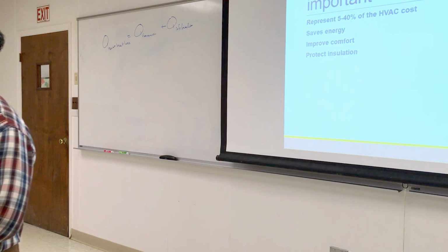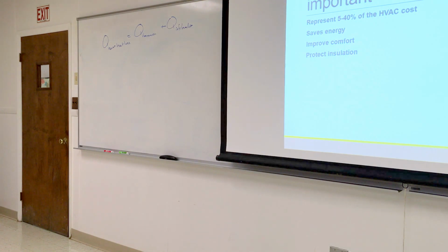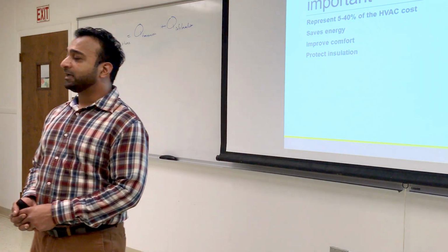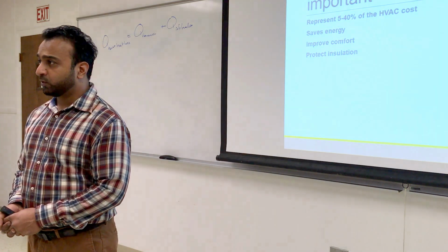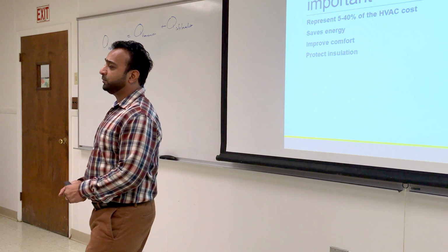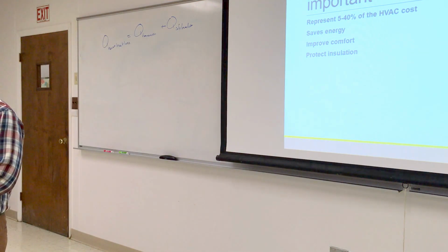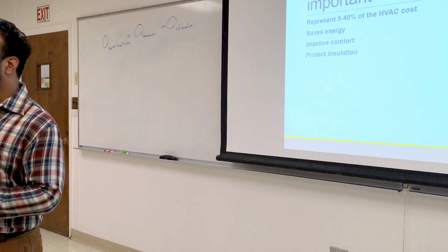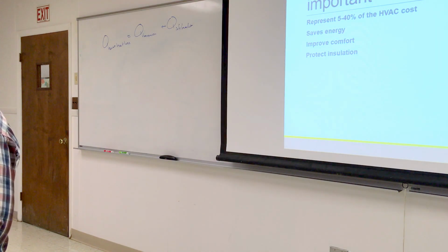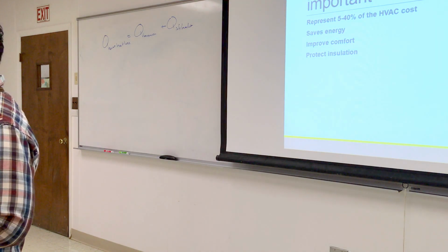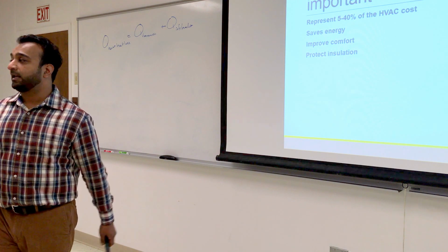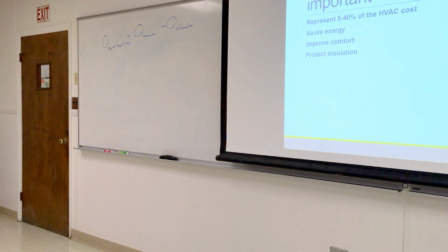Also, air leakage is not a good thing because it will ruin insulation. What does air from the outside have in it? Moisture. Moisture, after a while, depending on the weather conditions, will accumulate inside your insulation and ruin it. What happens to the insulation if it's saturated with water? Remember when we said earlier that if you have wood or cork as an insulator, it will absorb liquid over time. What happens if you have liquid? It will conduct electricity, and you also will conduct heat. So you fill those voids that you're depending on to insulate. And that's also a good environment for mold and fungi.